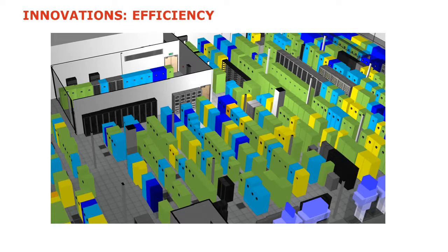So to Steve's point, what this tool will do is collect data from a number of different points, both on those cabinets, around the data center hall itself, and very specifically in the cooling units, the downflow or CRAC units as they're sometimes called, and really try and balance the amount of energy that's being delivered in terms of the cooling and the cooling duty and match that against the requirements of the IT equipment across the floor in different areas.